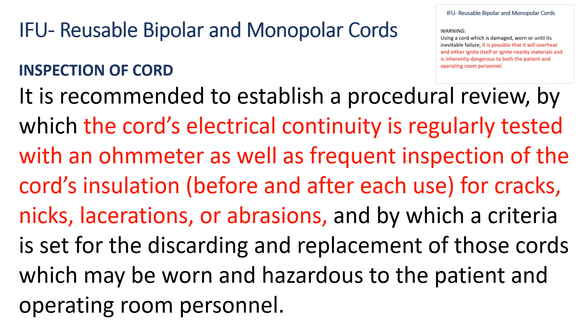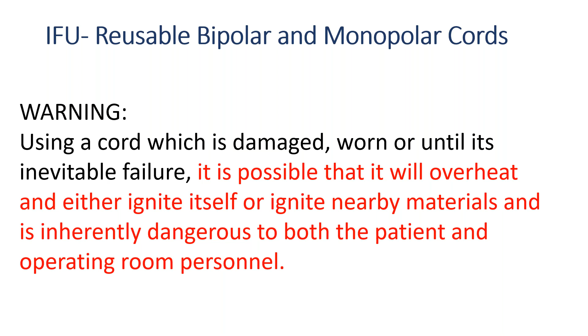They were kind enough to put a warning in the IFU, and it said that using a cord which is damaged or worn, or using it until its inevitable failure, it is possible that it will overheat and either ignite itself or ignite nearby material, and is inherently dangerous to both the patient and the operating room personnel. This is a point that is not just for the patients. Actually, when we have a surgical fire, the staff could be part of the damage.